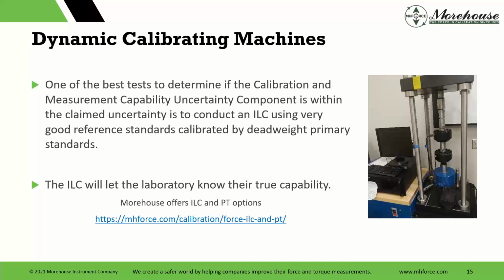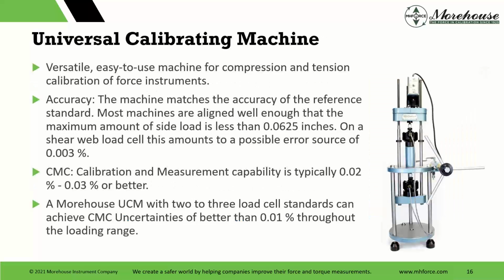One of the best tests to determine if the calibration and measurement capability uncertainty component is within the claimed uncertainty is something people are not doing as much. If you have one of these machines and you or a lab is claiming a number such as 0.2 or 0.5, the best way to prove it is to do an interlaboratory comparison or proficiency test. That will let a laboratory know their true capability, and we offer ILC and PT options.